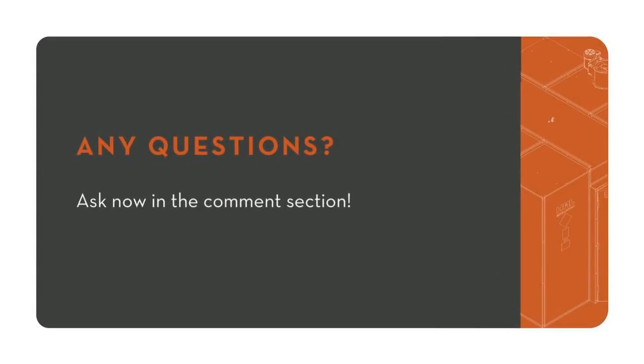I see that I have a couple. So for Andy, I'd asked about space conditioning heater, extraction room equipment heater. So it would be an equipment heater or an equipment chiller. Those sometimes need to be turned off given certain conditions. We see a lot of people, if they reach that 25% threshold, those heaters, those ancillary components that wouldn't be inside the room, but would be connected to the equipment inside the room, they would need to shut off so that that system can shut down. And if that doesn't answer your question, Andy, I could definitely delve further into that.